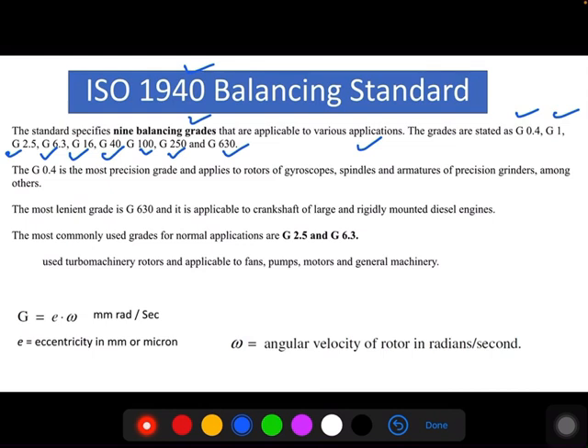G0.4 is the most precision grade and it mainly applies for the rotors of gyroscopes, spindles, armatures, precision grinders among others. The most lenient grade is G630 and is applicable for the crankshaft of large and rigidly mounted diesel engines. In industries, the most commonly used grades are G2.5 and 6.3, but in recent days, G2.5 is mainly used for the turbo machinery rotors and also in general fan application, pumps, motors, and general industries. So G2.5 is most preferable in recent days.